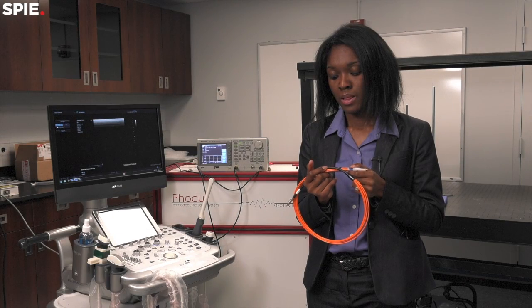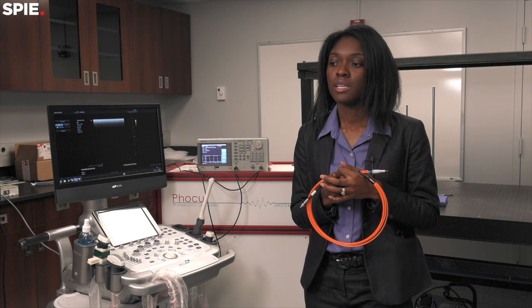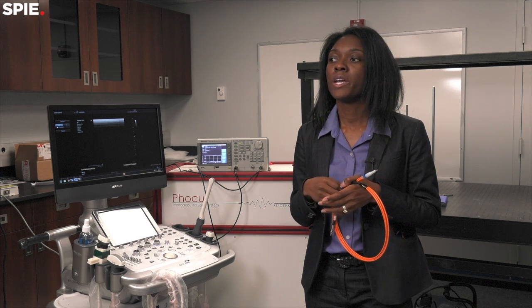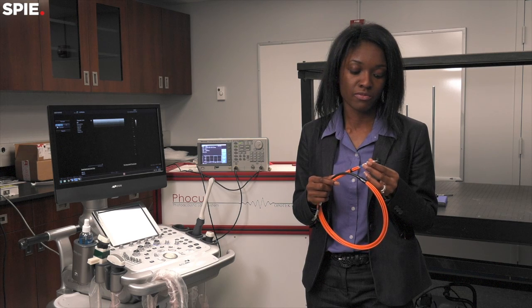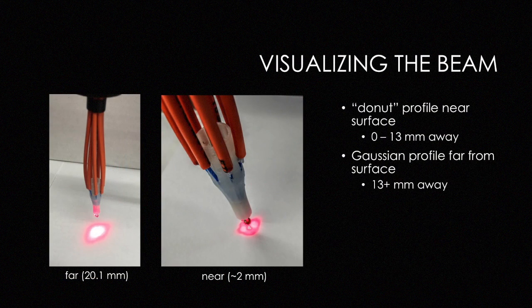We can make our specialized light delivery systems compatible with any surgical tool. In that case, we're not bringing any new surgical instruments, but we're bringing new imaging devices and imaging technologies like the optical fibers that need to surround the tool. You want to make sure that the fibers are creating a nice uniform optical profile because you want to avoid any hot spots to avoid damage to whatever tissue might be in the path of the laser light.